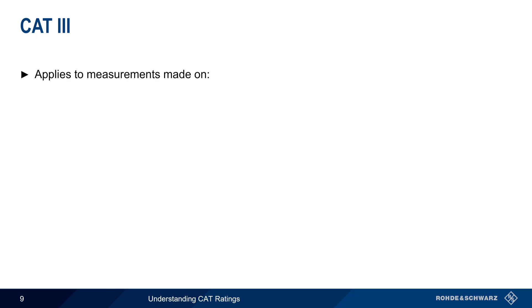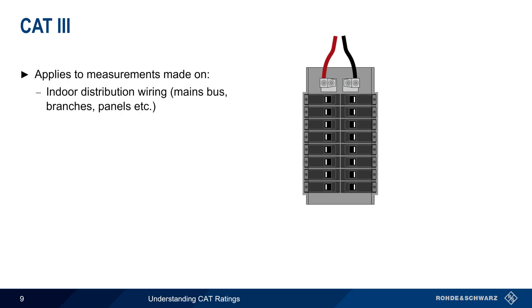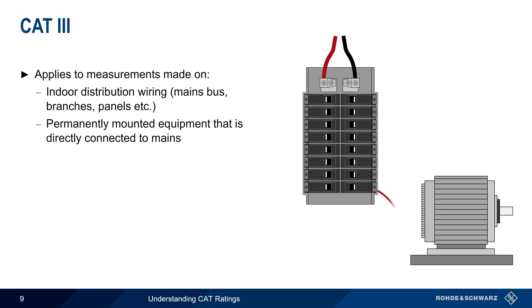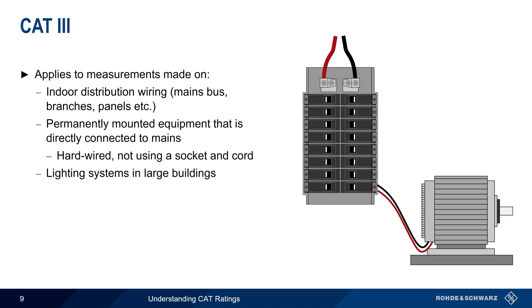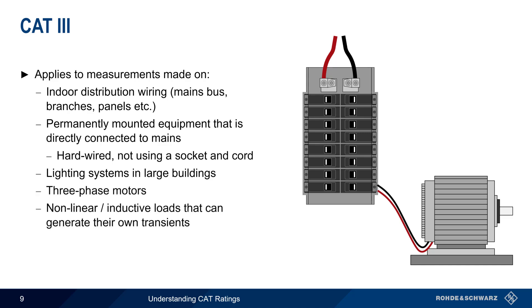CAT 3 applies to measurements made on indoor distribution circuits, such as on the mains bus, branches, panels, etc. This category also applies to permanently mounted equipment that's directly connected to mains — that is, equipment that's hardwired, not plugged in using a socket and power cord, as we saw for CAT 2. Additional examples of CAT 3 measurement environments include lighting systems in large buildings, three-phase motors, and any nonlinear or inductive loads which can generate their own transients.